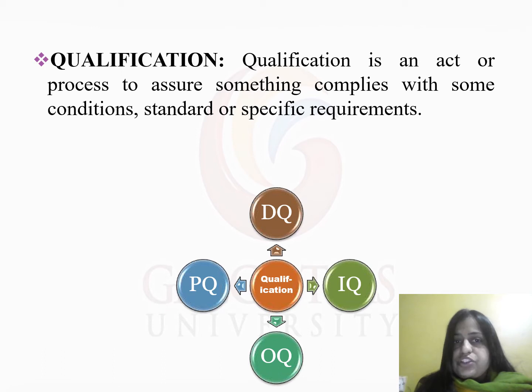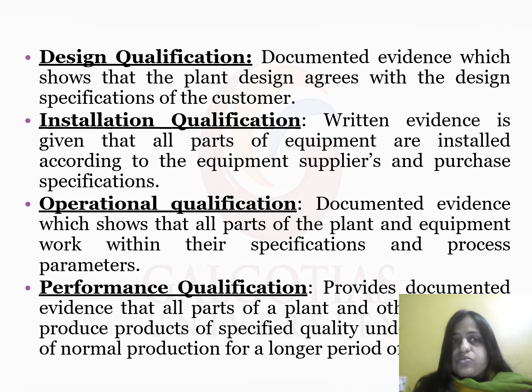Qualification is an act or process to ensure something complies with some standards, a condition or specific requirement. So qualification includes design qualification, installation qualification, operation qualification and performance qualification. Design qualification is documented evidence which shows that the plant design agrees with the design specification of the customer. Installation qualification: written evidence is given that all parts of the equipment are installed according to the equipment supplier and purchase specification. Operational qualification is documented evidence which shows that all the parts of plant and equipment work within their specification process parameters. Performance qualification provides documented evidence that all parts of plant and other produce product of specific quality under control under normal production for a longer period of time.